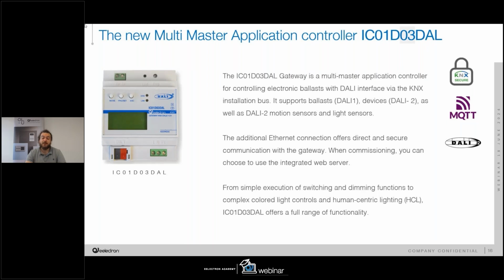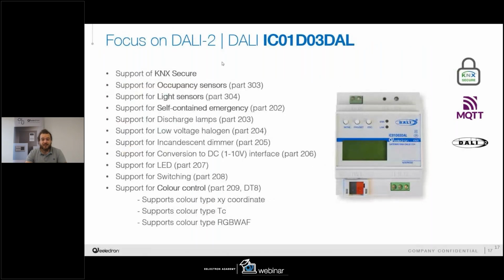This DALI gateway is a multi-master application, which means that thanks to the DALI2 protocol, now we can also integrate motion sensors, brightness sensors, movement detectors with motion and brightness, push button interfaces, but also some generic probes like for the control of temperature, humidity, and so on. As said, this can be done thanks to the update of the DALI2 protocol that is now ready for every one of our devices.